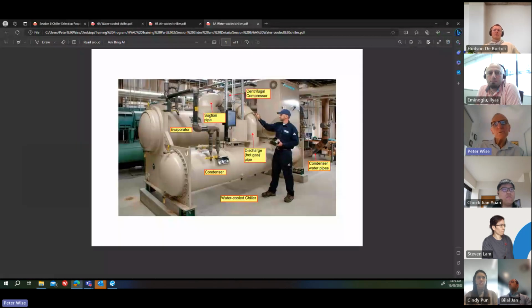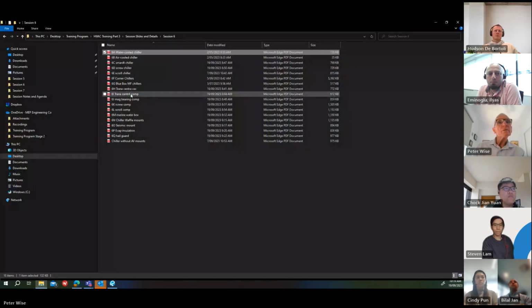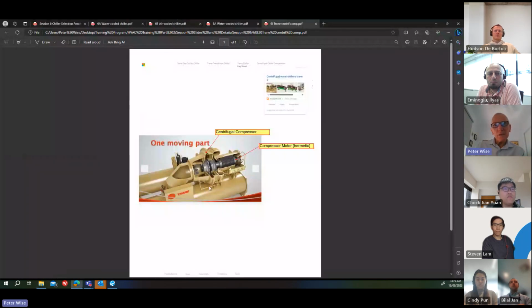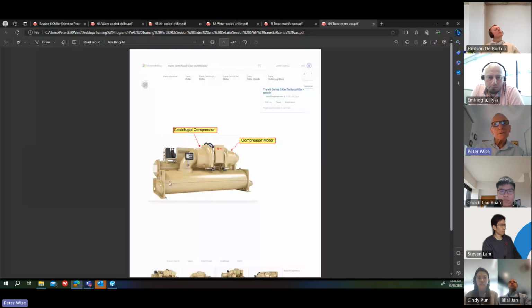It's the water-cooled chiller with a centrifugal compressor. It's a bit hard to see the compressor. It's sitting up there. I've got some better pictures of that. This is a cutaway of a Trane centrifugal compressor. So this is a suction pipe here, the compressor's in here, and this is the motor. So that's a hermetic type motor because the refrigerant passes through the motor as well. And that's the Trane compressor, not cut away. So you've got the evaporator down here and so on, evaporator, condenser. So they're generally quite large chillers.